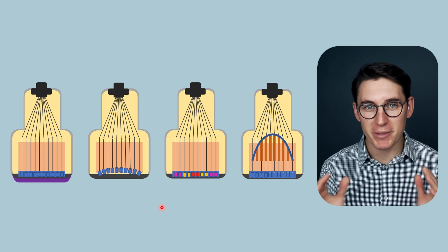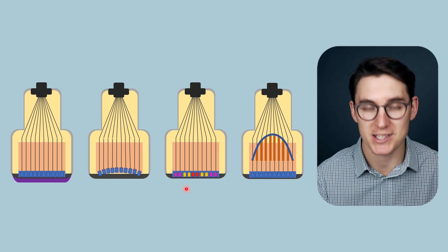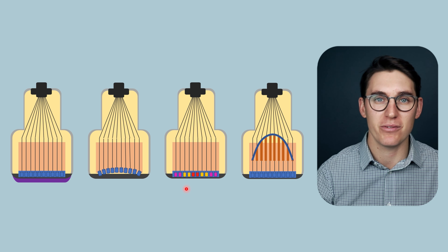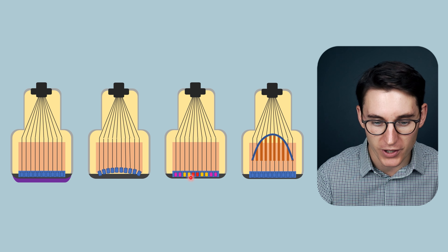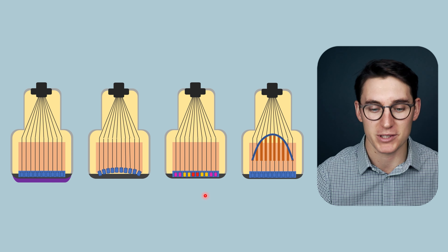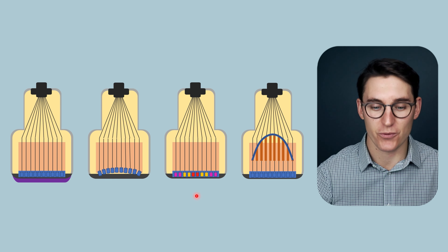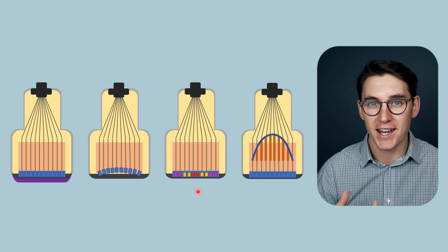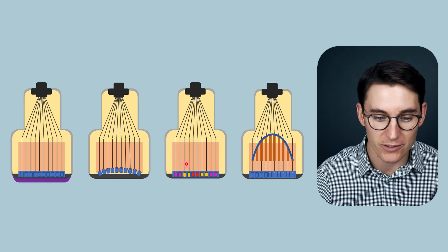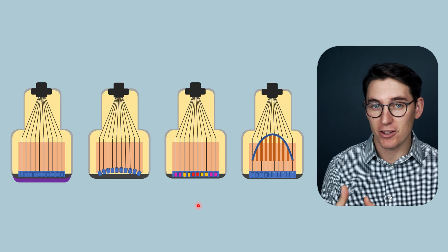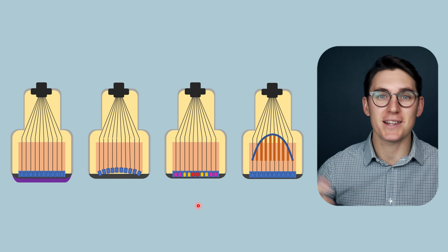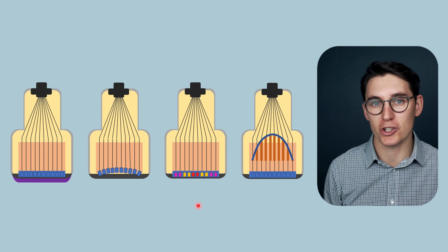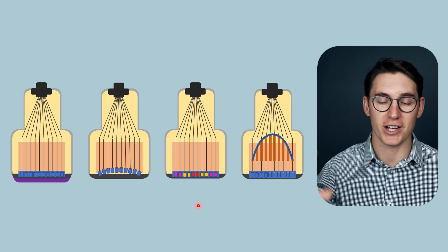The third mechanism is by manipulating the diameter of the transducer elements used to create the ultrasound pulse. Changing the diameter changes the depth of the focal zone. For example, firing only the red transducer elements — a very narrow diameter — gives a shallow focal zone. Firing both red and orange elements increases the diameter by a factor of three, increasing focal depth. Firing all elements makes the focal zone even deeper. We can repeat this cycle and superimpose the images, providing good resolution within each focal zone.